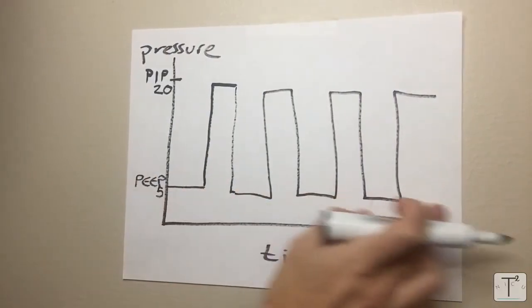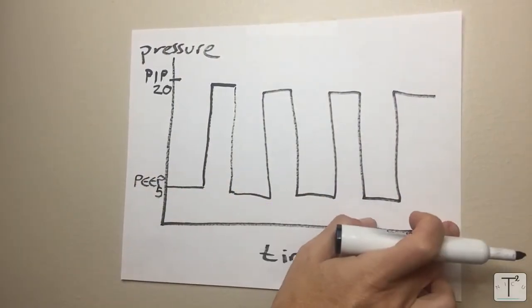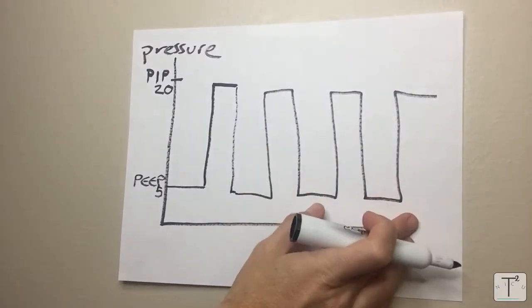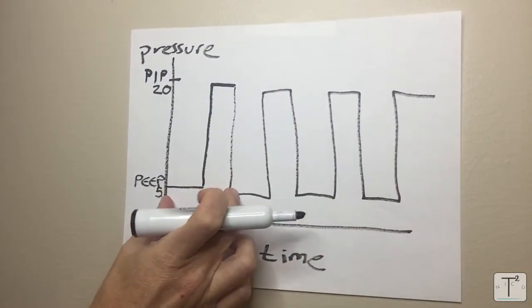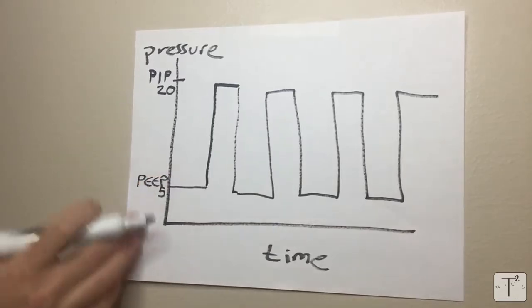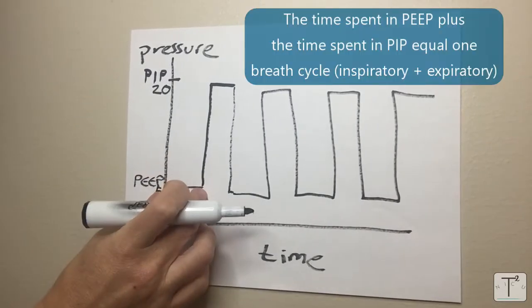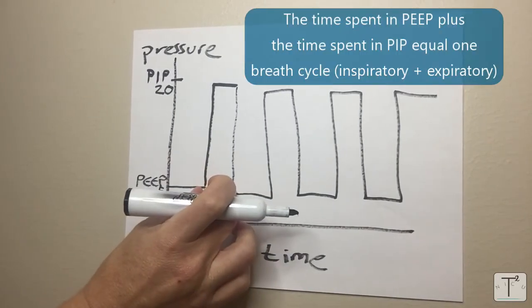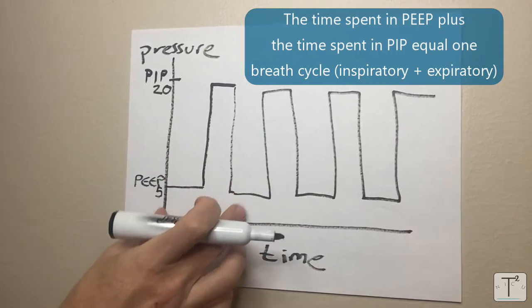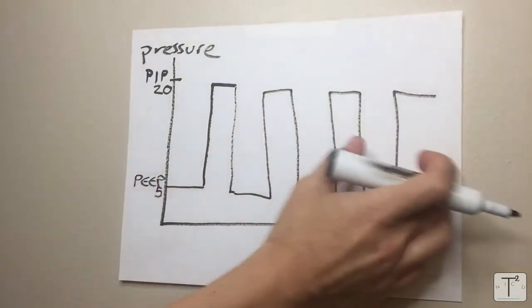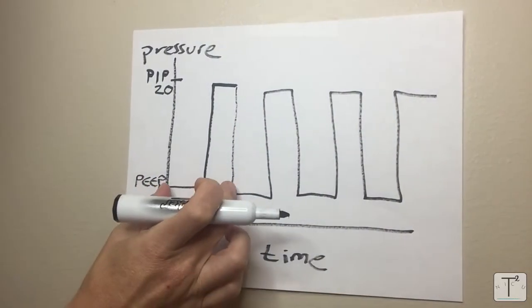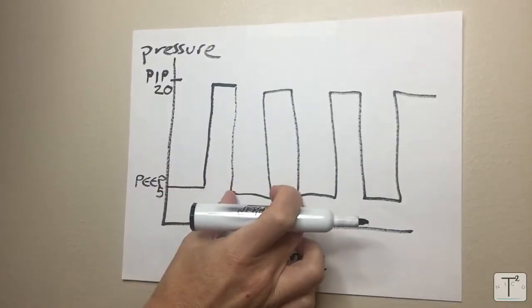If the rate that you set on the machine is 30 then 60 divided by 30 is 2 so each breath will last for two seconds. That would be the time spent in PEEP plus the time spent in PIP would equal a total of two seconds. If you set the rate at 60 then obviously each full breath would only be one second.